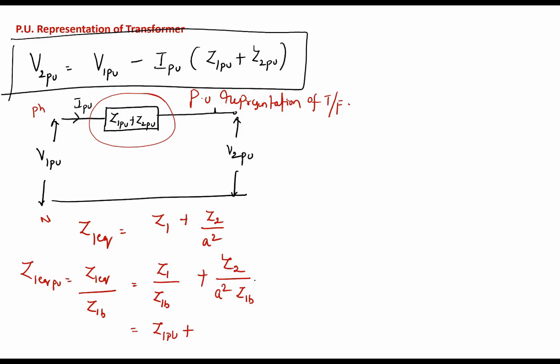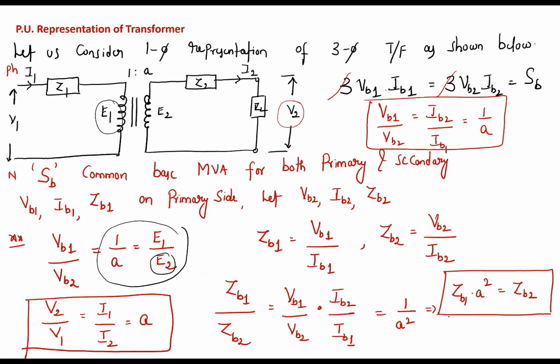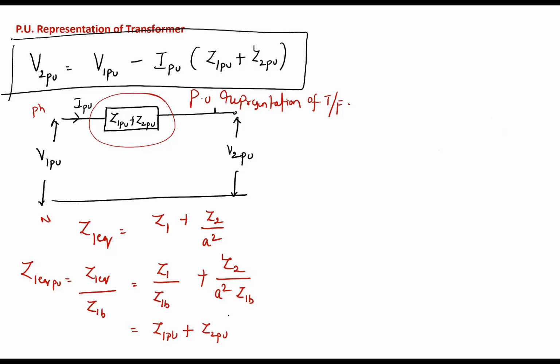A square into Z1 base is Z2 base. So this will become Z2 per unit. If you recollect this one, A square into Z1 base, don't get confused, somewhere I am writing ZB1, Z1B, both are same. So A square into Z1 base is Z2 base, which will give you Z2 base is Z2 per unit. So if you calculate the per unit value of the equivalent impedance on primary side, you are going to get Z1 per unit plus Z2 per unit.